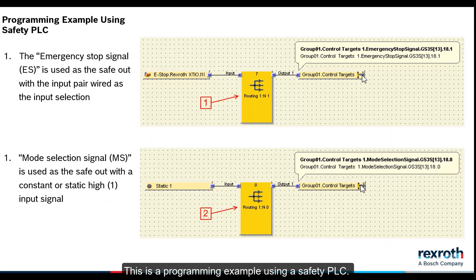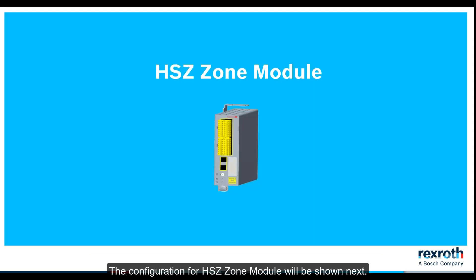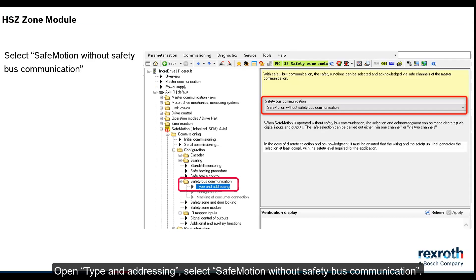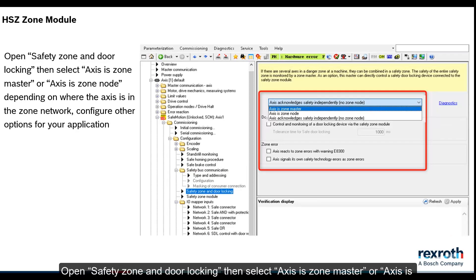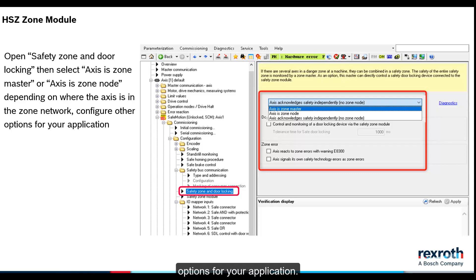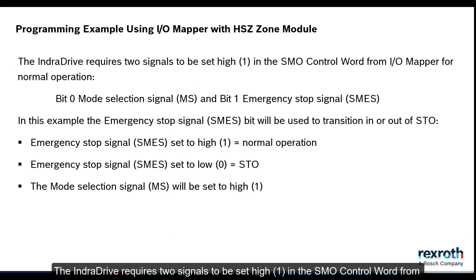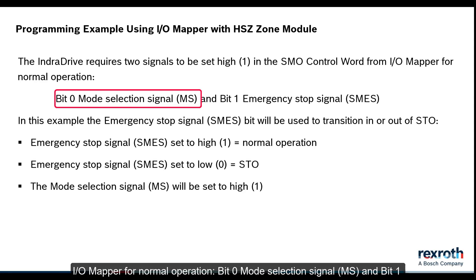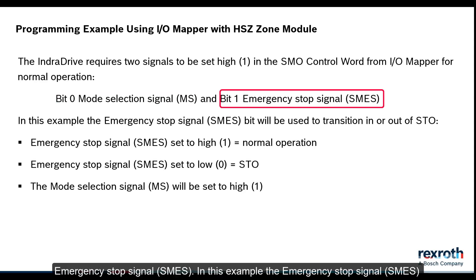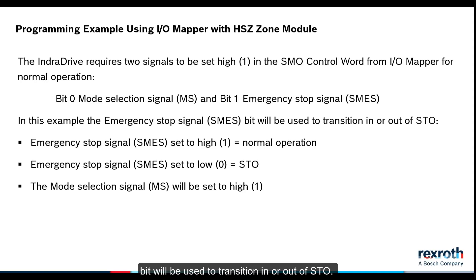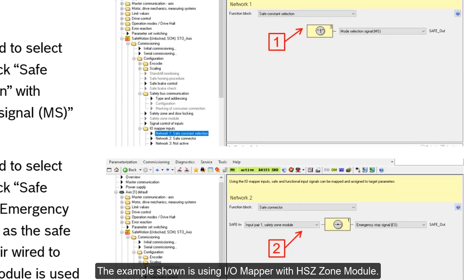This is a programming example using a safety PLC. The configuration for HSZ zone module will be shown next. Open type and addressing. Select safe motion without safety bus communication. Open safety zone and door locking, then select axis is zone master or axis is zone node, depending on where the axis is in the zone network. Configure other options for your application. The IndraDrive requires two signals to be set high in the SMO control word from IOMapper for normal operation: Bit 0, Mode Selection Signal MS, and Bit 1, Emergency Stop Signal SMES. In this example the SMES bit will be used to transition in or out of STO. The example shown is using IOMapper with HSZ zone module.